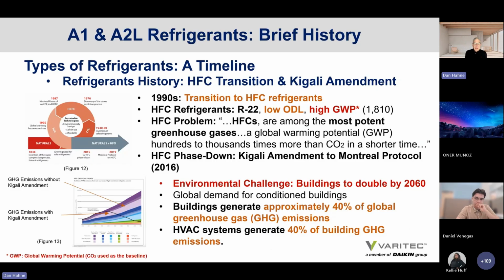So when there was a regulation of CFCs and HCFCs, a transition refrigerant was sought after, and that is HFC refrigerants. HFCs were a good bridge since the initiation of the Montreal Protocol because they have a low ODP level. However, they have a high global warming potential. HFCs are among the most potent greenhouse gases, with a global warming potential hundreds to thousands of times more than CO2 in a shorter time. Consequently, because of this pressing need and the acceleration of climate change we're experiencing, the HFC phase down occurred through the signing of the Kigali Amendment to the Montreal Protocol in 2016. Why? Why was this move to reduce the GWP caps on refrigerants?